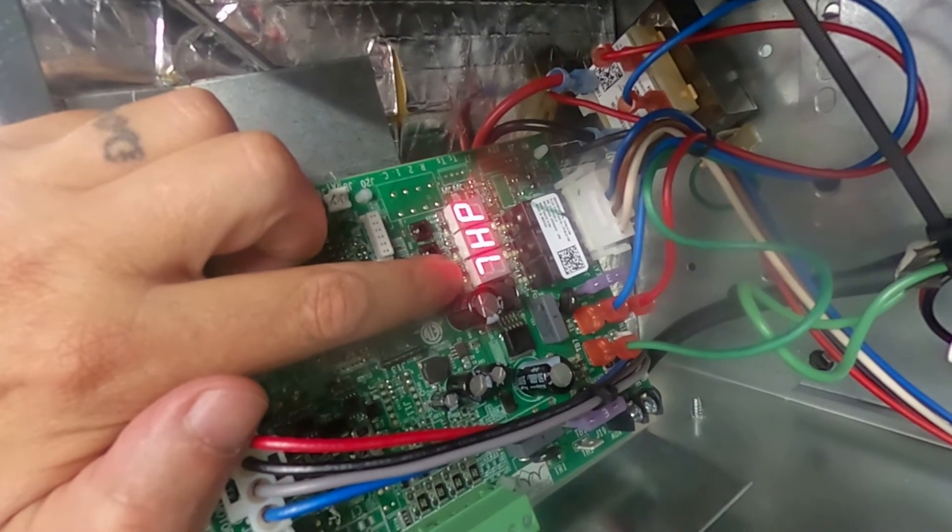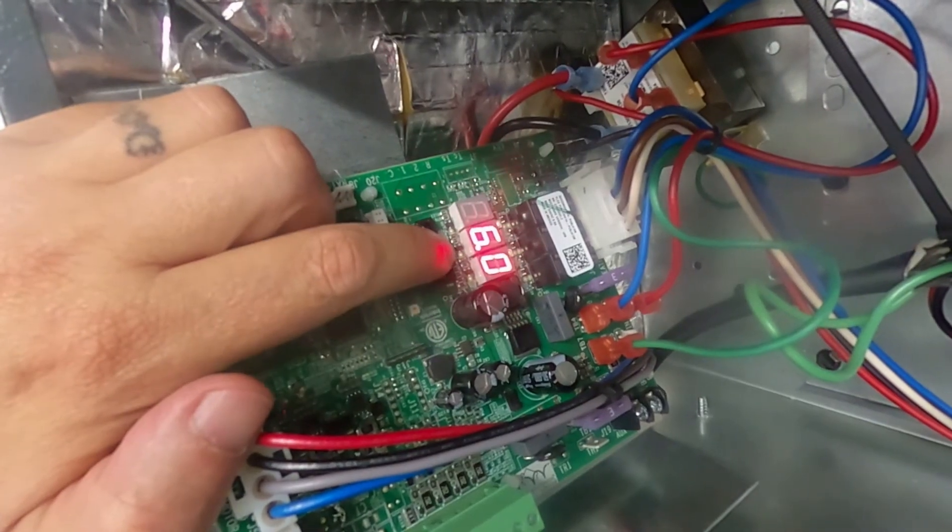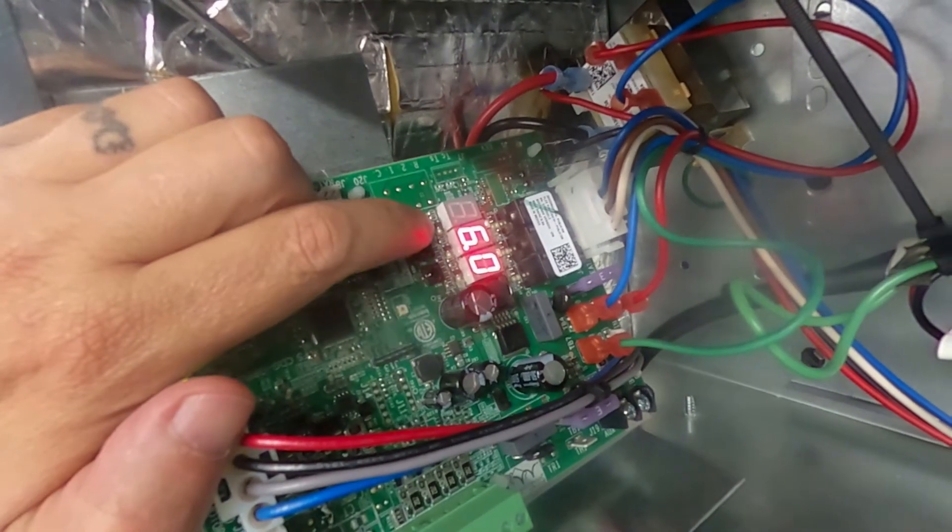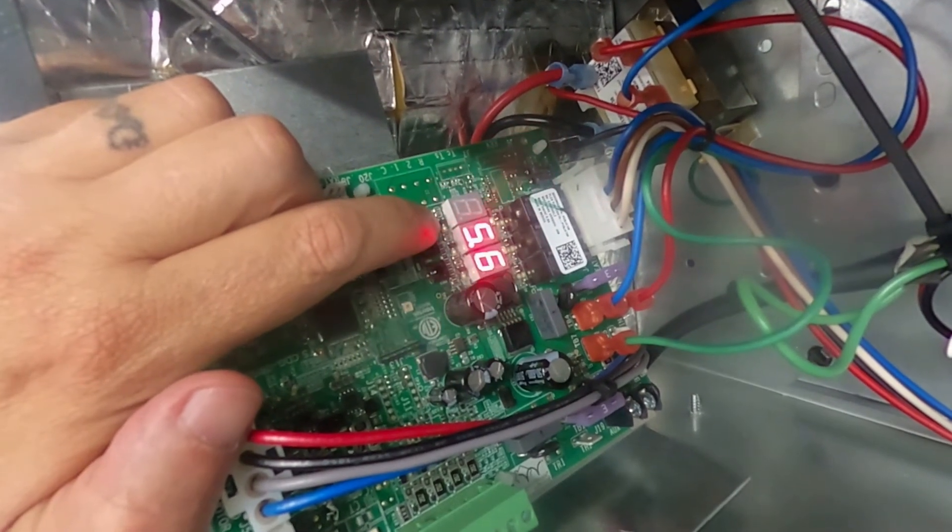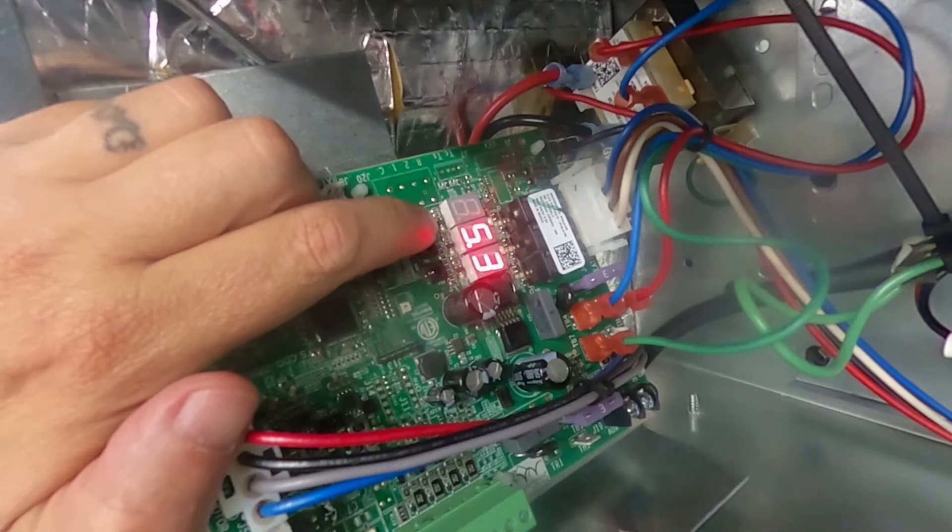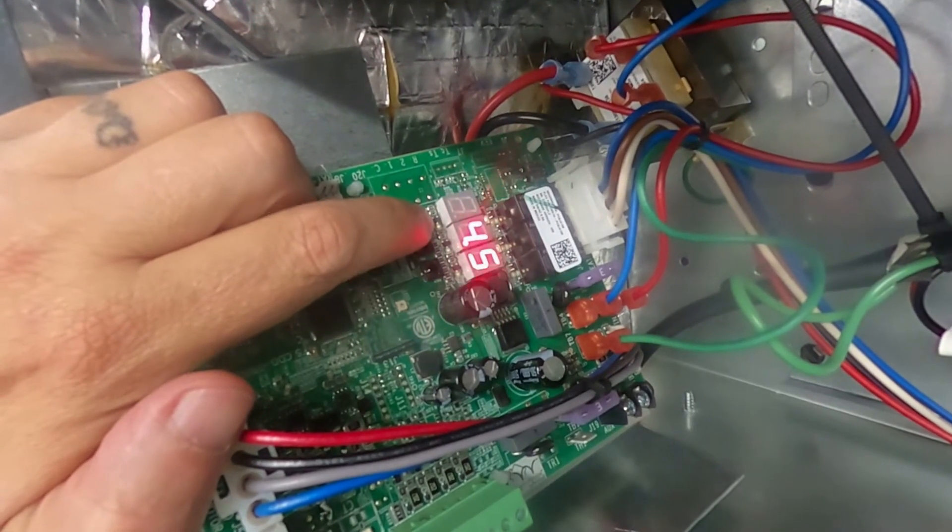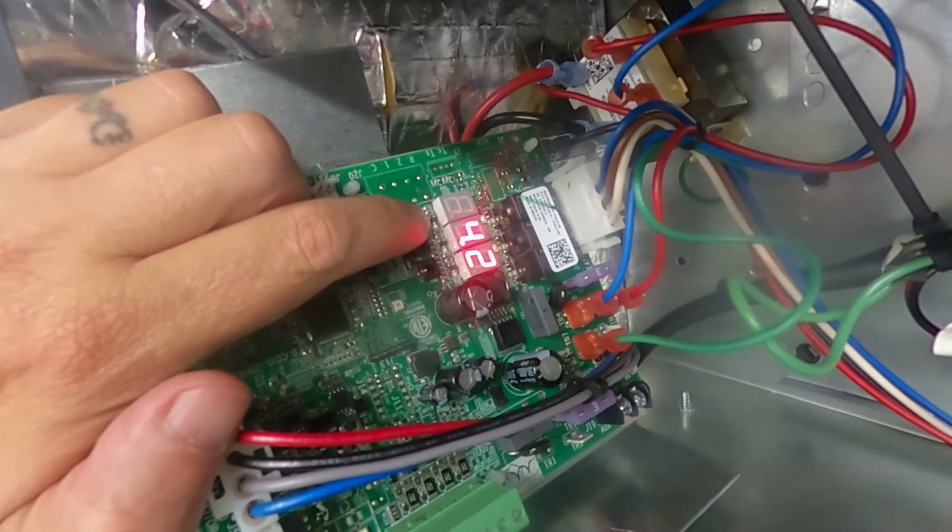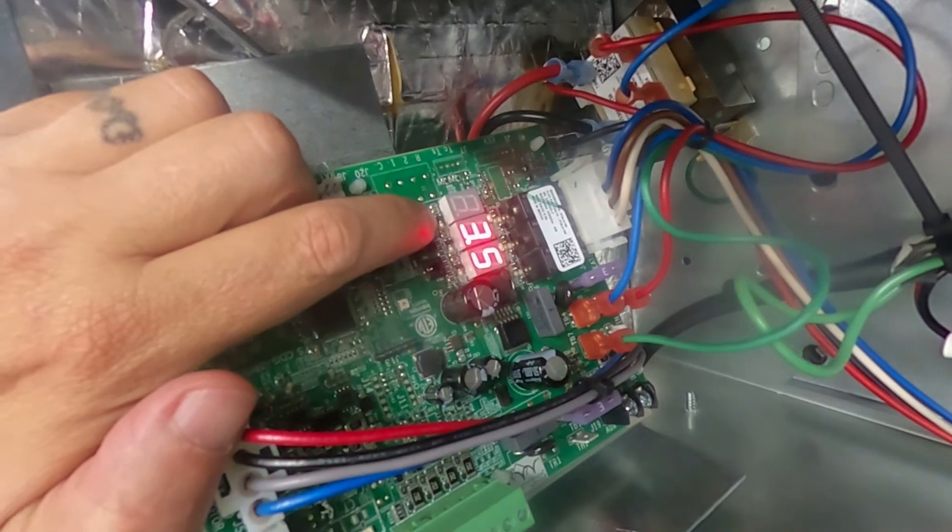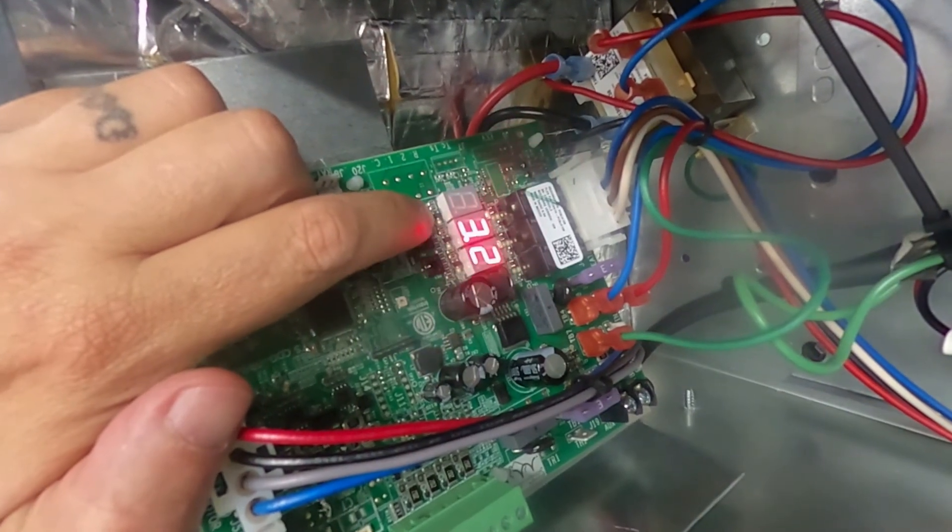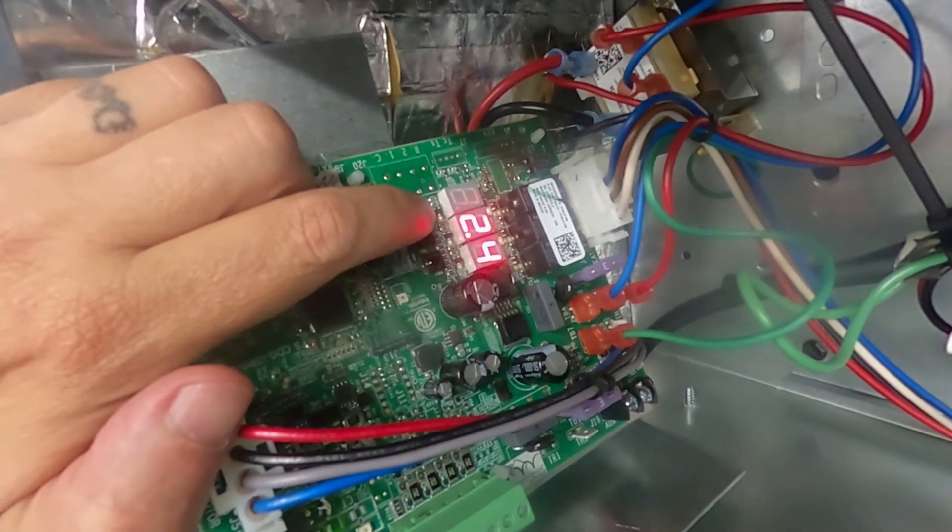We're back at ODS. I'm going to scroll now until I have TON for tonnage. You'll see it's 6.0. This does one ton, 400 CFM. In this case, I have a two. It doesn't mean I have to choose 2.0. If you have a higher sensible, you can do a 2.1 or 2.2.